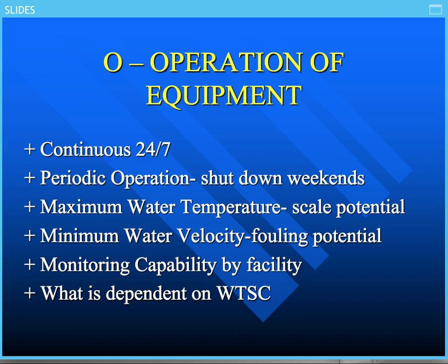So you've got to keep the film pack fill in the cooling tower clean as well. Could I have the next one, please? This particular slide is the operation of the cooling water system, and what type of operation are we actually encountering here? Is it continuous 24/7, or is it dealing with periodic shutdown? And with periodic shutdown, how does that impact my water treatment program? If we want to have a really first-rate cooling water treatment program, you have to consider the fact that it may be shut down over weekends, or periodically.